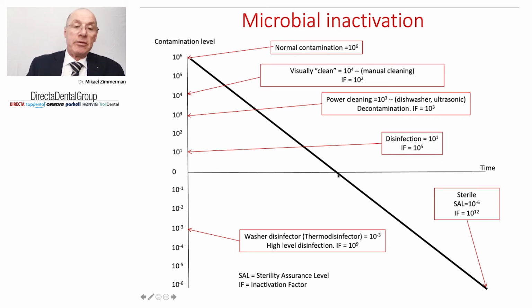On the bottom side, we cannot measure; we can stop the process at different steps to measure how many microorganisms will still be on the instruments. But below zero, we can only do a theoretical calculation. And this theoretical calculation will be the safety margin on your instruments.